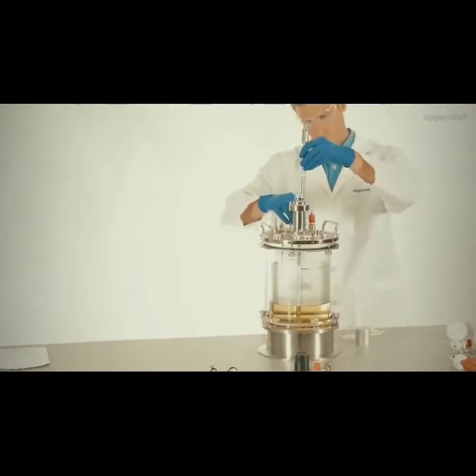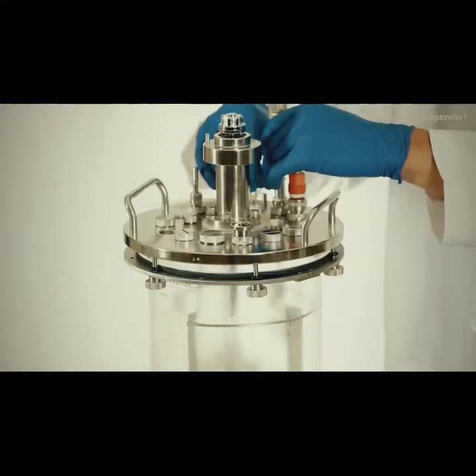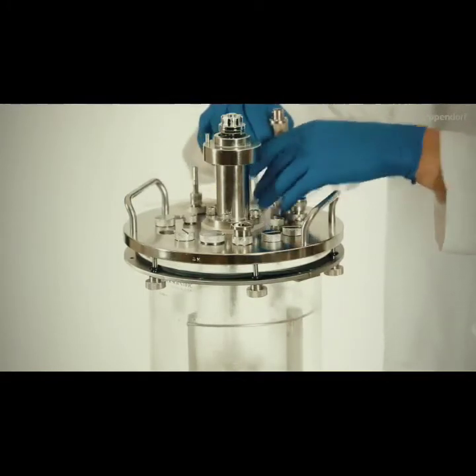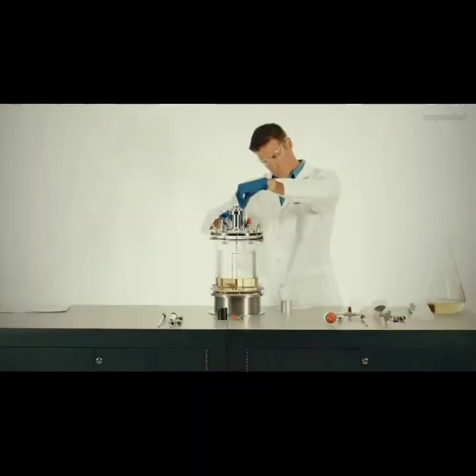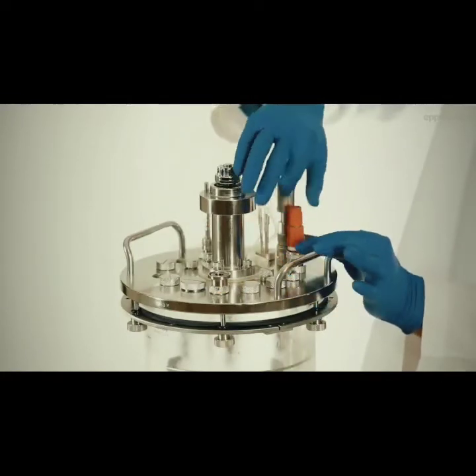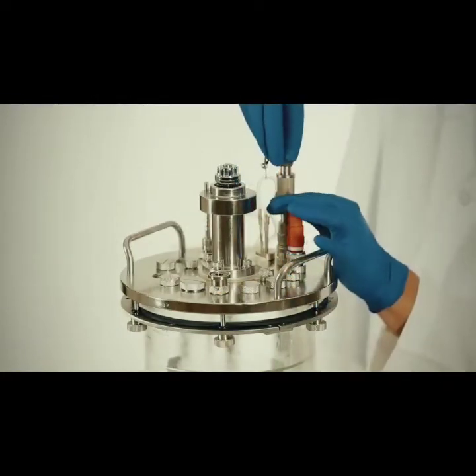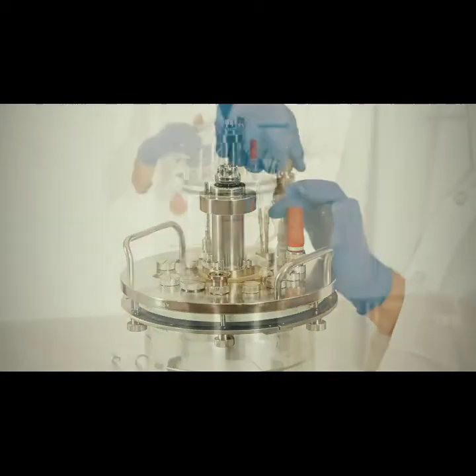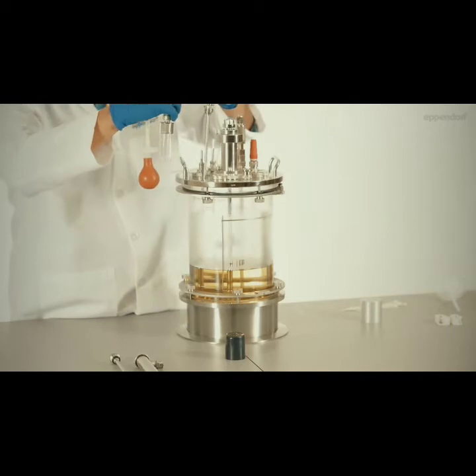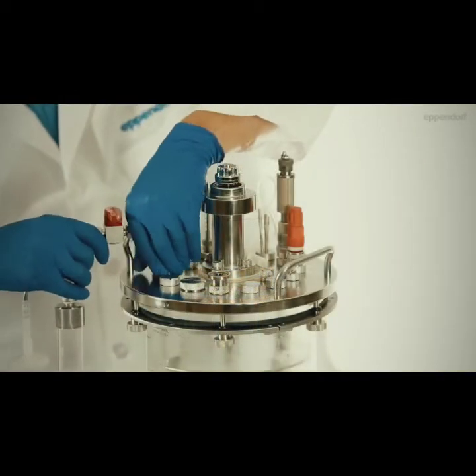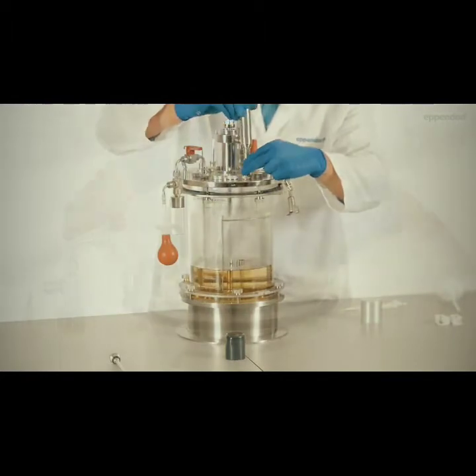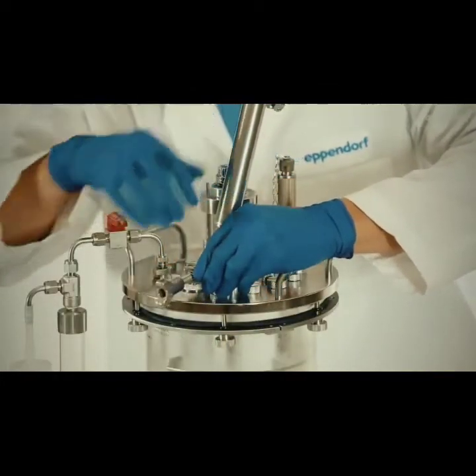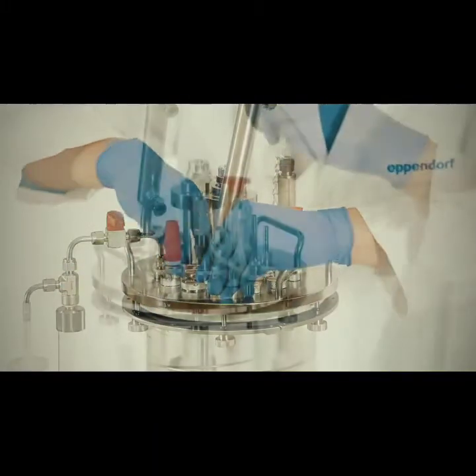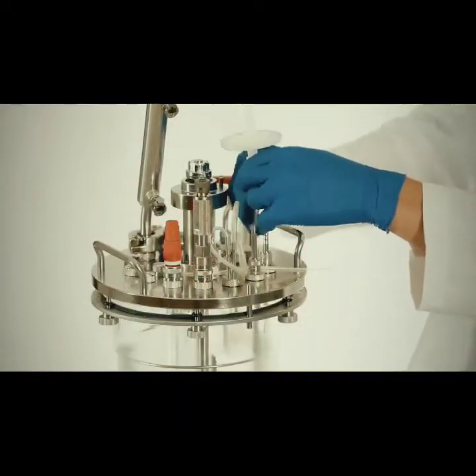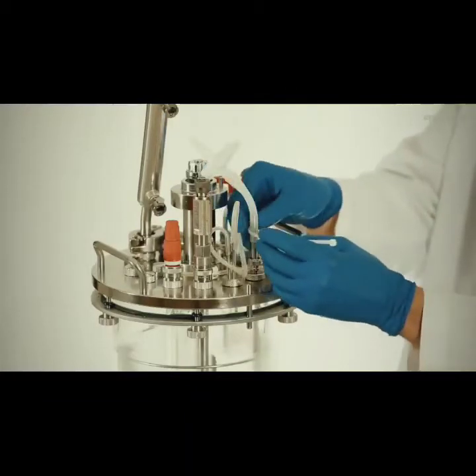Carefully install the DO sensor. Cover both the pH and DO sensors with protective caps to protect them from the autoclave cycle. Install the sampling assembly. Install the exhaust condenser. Install a sparge filter on the sparge line and an exhaust filter on the top of the exhaust condenser.